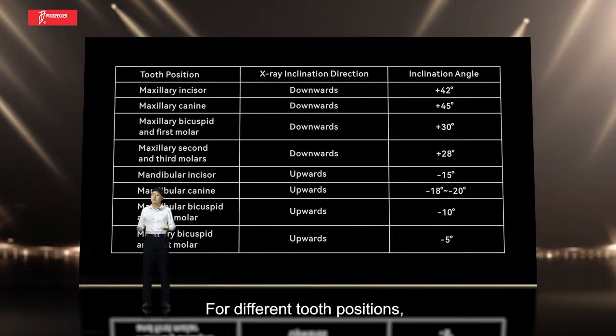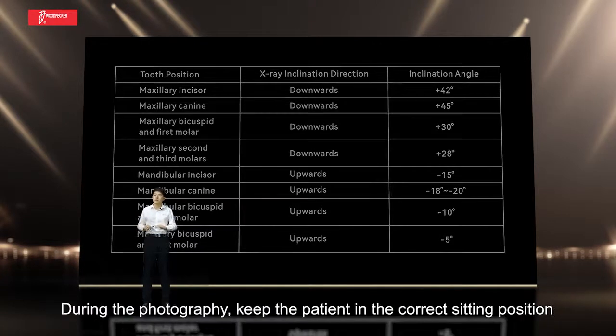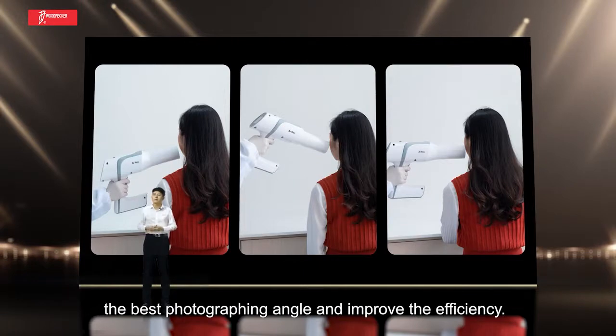For different tooth positions, we have made corresponding reference values for the photographing angle. During photography, keep the patient in the correct sitting position and adjust the dental X-ray machine to obtain the best photographing angle and improve efficiency.